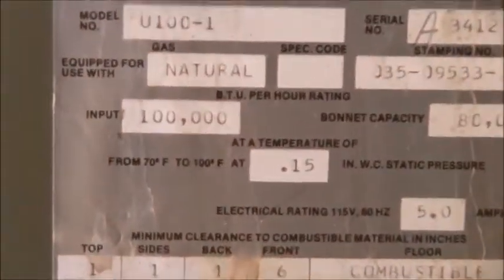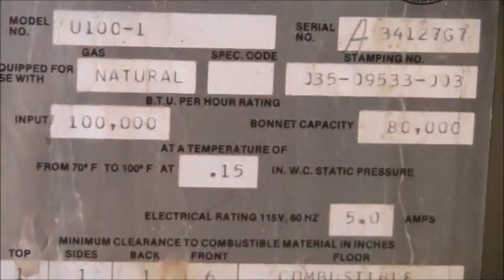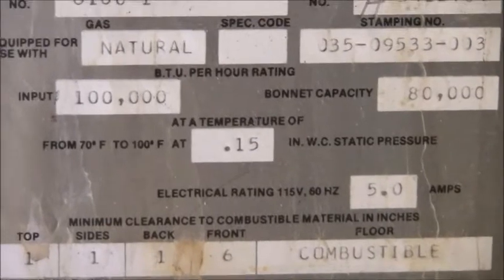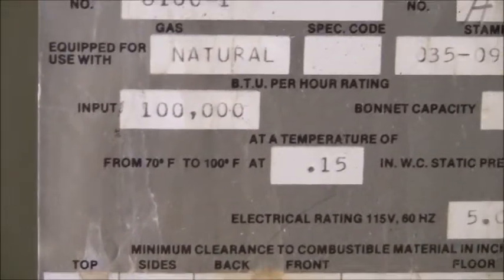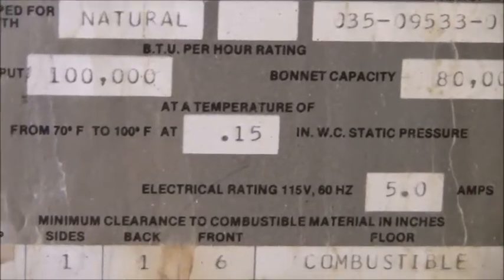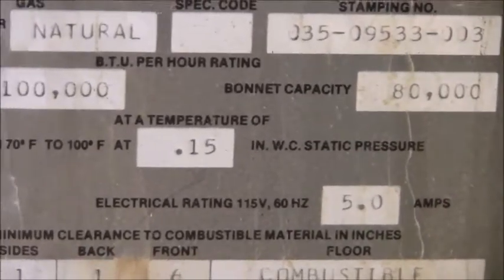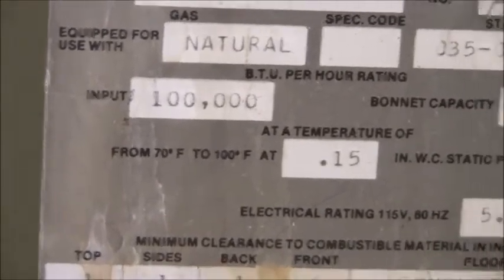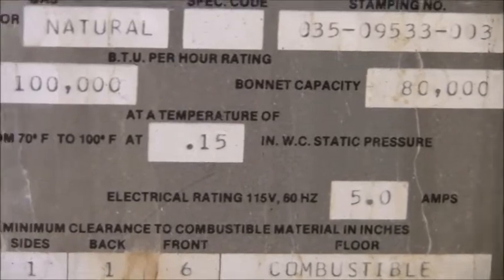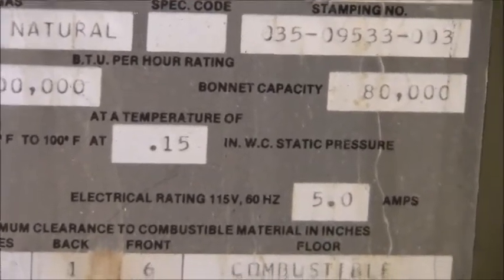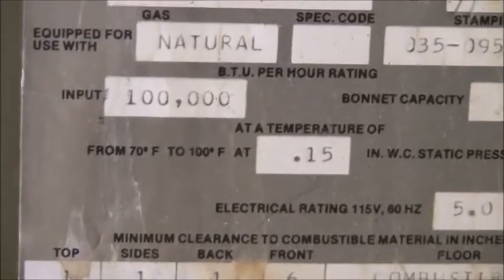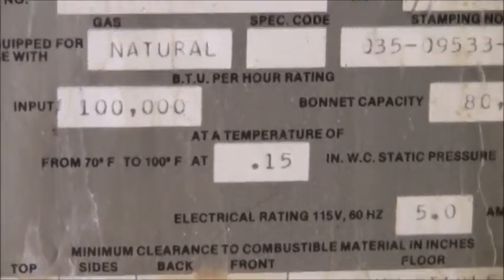On the furnace right here, there should be information about the rated external static pressure, but it doesn't have it. This just tells you the heat rise from 70 to 100 degrees at 0.15 inches of water. Okay, that's how much temperature rise we should get with a 0.15 inch water column static pressure. I'm unclear if that's a supply static pressure or exactly what static pressure that is.